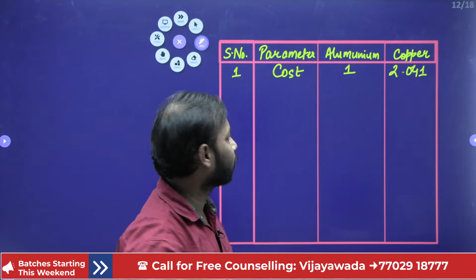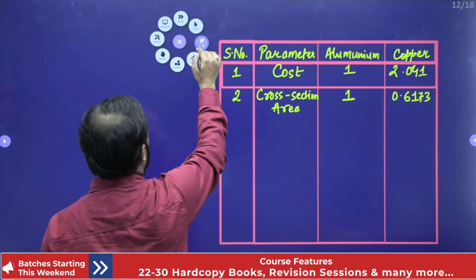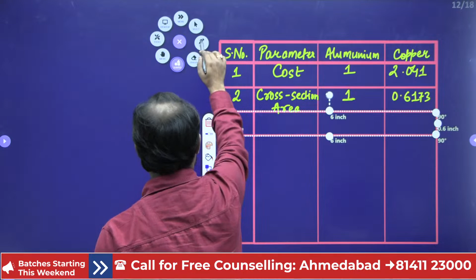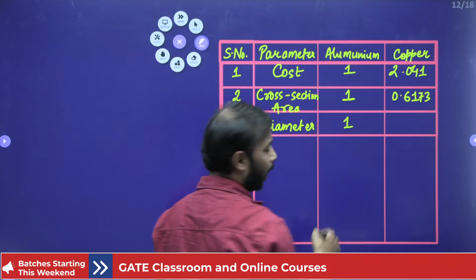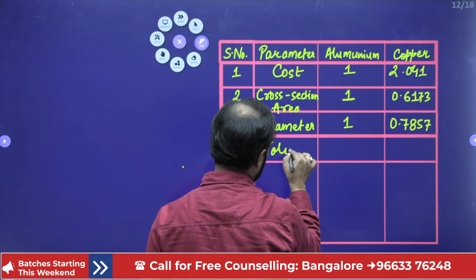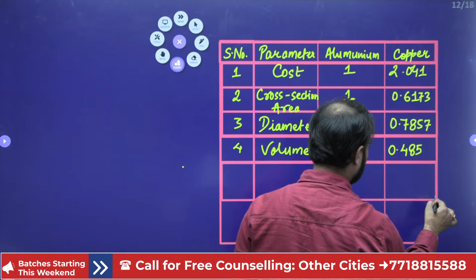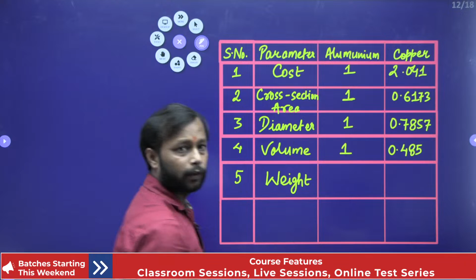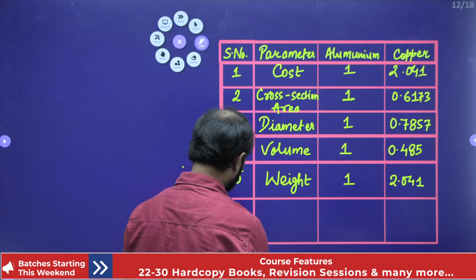Next one is the cross sectional area. If the cross section area of aluminium is taken as 1, then for copper it will be 0.6173. Next one is the diameter. If the diameter of aluminium is 1, then for copper it is 0.7857. Fourth is volume. If volume is 1 for aluminium, then for copper it is 0.485. Fifth one is the weight. If the weight of aluminium is 1, then it will be 2.041 for copper. And the last one is the strength. If this is 1, then for copper it is 1.56.